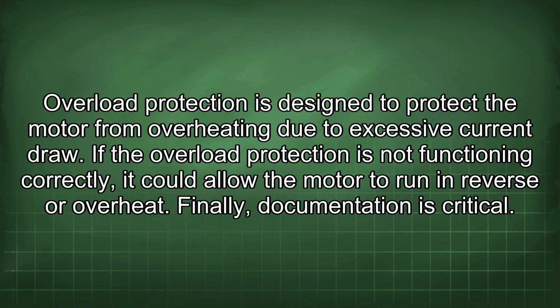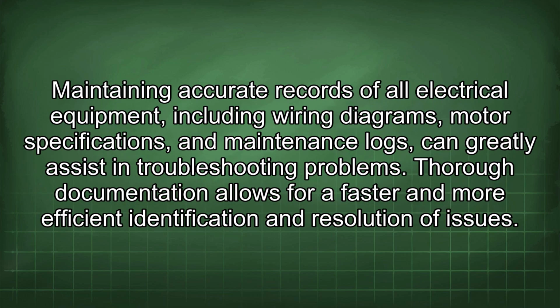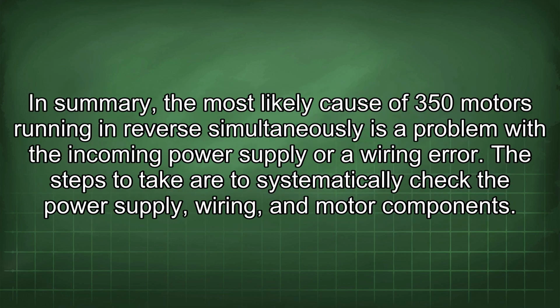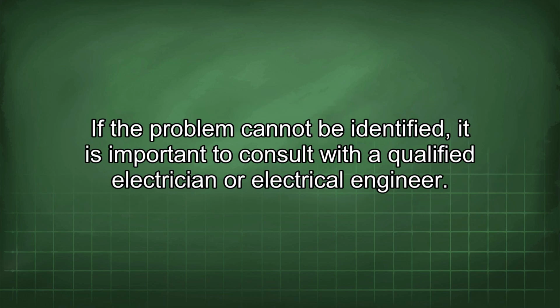Finally, documentation is critical. Maintaining accurate records of all electrical equipment, including wiring diagrams, motor specifications, and maintenance logs, can greatly assist in troubleshooting problems. Thorough documentation allows for a faster and more efficient identification and resolution of issues. In summary, the most likely cause of 350 motors running in reverse simultaneously is a problem with the incoming power supply or a wiring error. The steps to take are to systematically check the power supply, wiring, and motor components. If the problem cannot be identified, it is important to consult with a qualified electrician or electrical engineer.